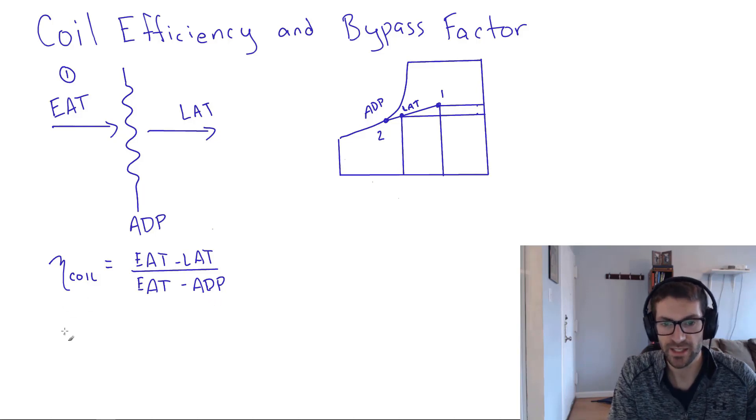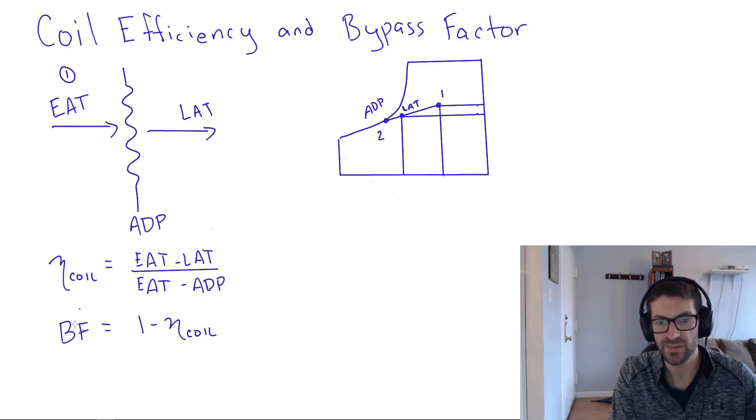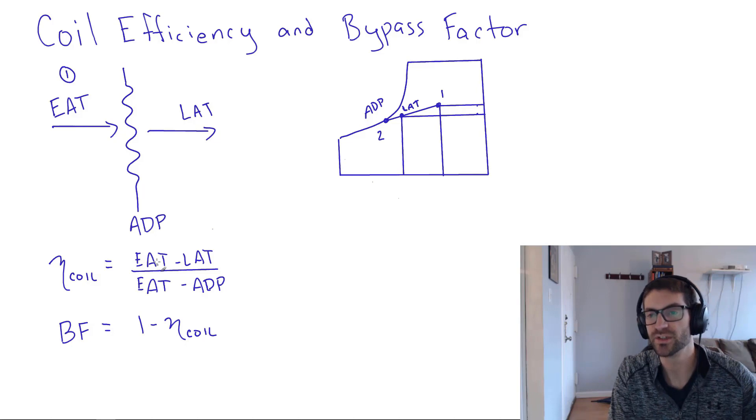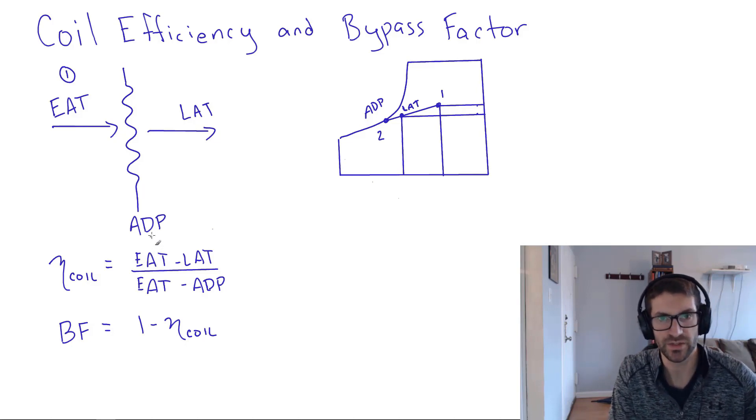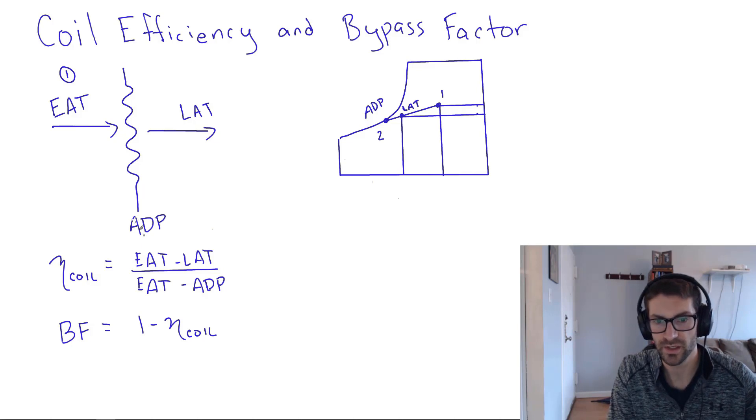The bypass factor is the complement of the coil efficiency. It's one minus the coil efficiency. So if a problem speaks to coil efficiency, you want to think about this ratio. If it speaks to bypass factor, it's the exact same concept. But we would say that if it's an 80% efficient coil, then it has a 20% bypass factor. That's the same information offered using different words.